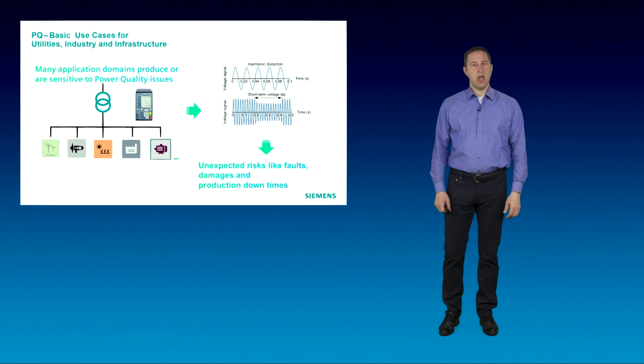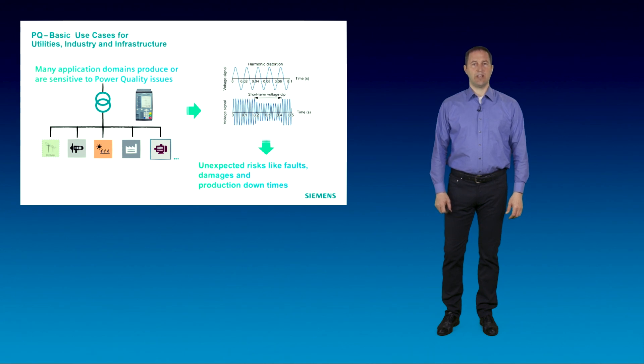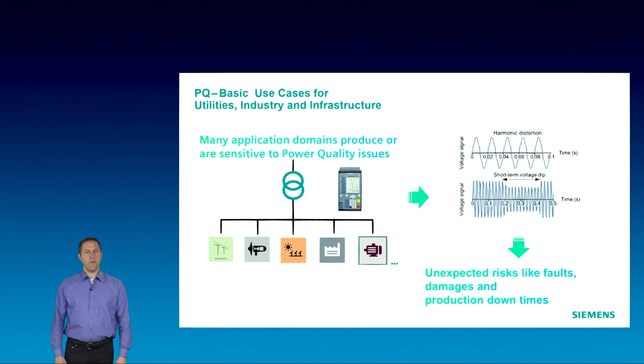Some examples: circuit breaker operations within the grid or start-up behavior of huge motors can lead to voltage dips. Feeding of renewable energies can lead to voltage swells and harmonics. Non-linear loads and variable speed drives in industry could cause harmonic distortions. Unsymmetric loads within the three-phase system leads to voltage unbalances.